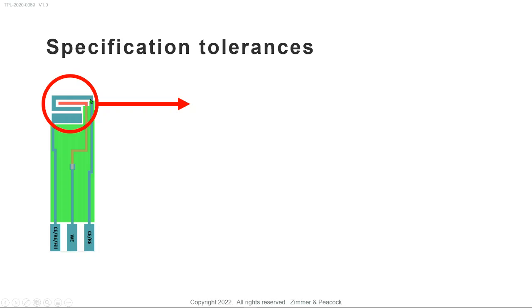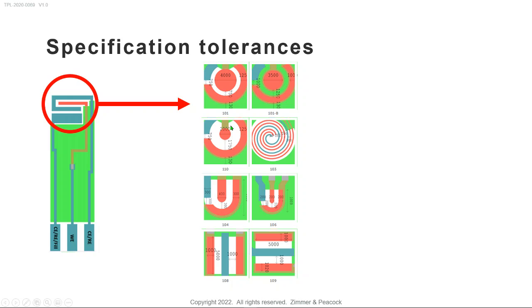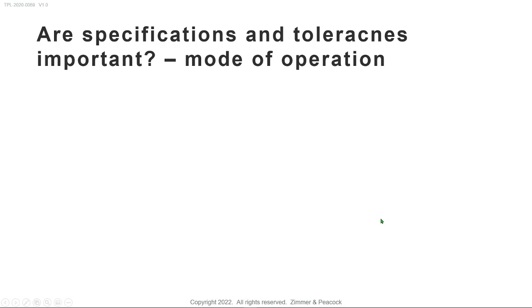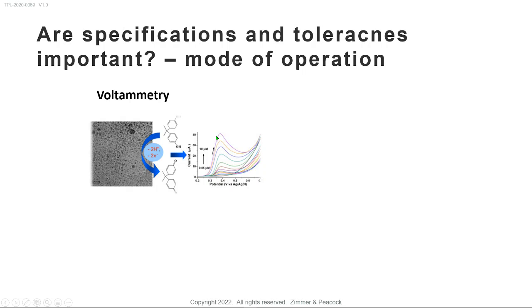In terms of tolerances, people can sometimes be very stringent. When we talk about tolerances, we're referring to the very important parts of a screen printed electrode, often around the working, counter, and reference electrodes. We understand that people have a desire to control these conditions. The first question is: are tolerances important? The answer is yes and no — it depends. A common mistake is to think about the screen printed electrode in isolation of the entire technology stack.